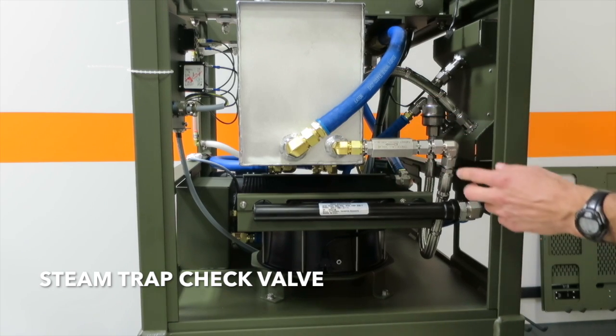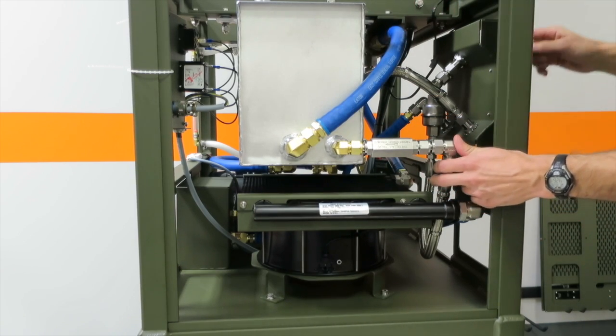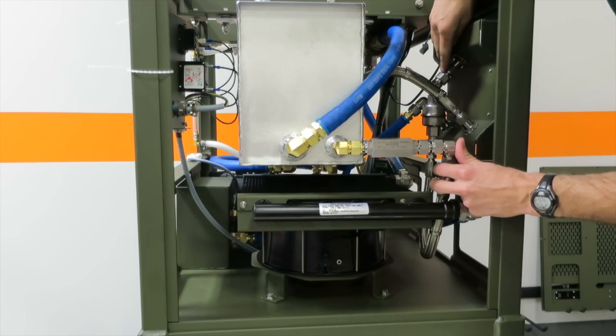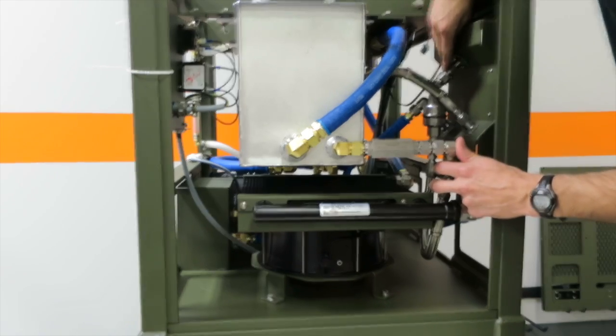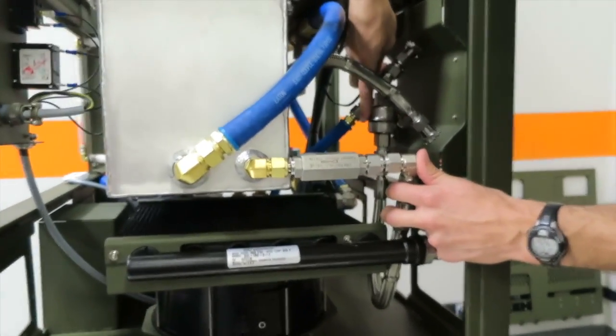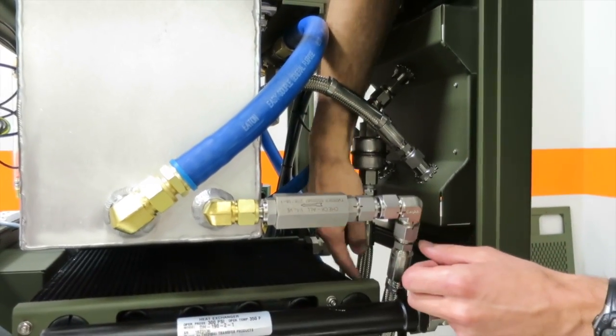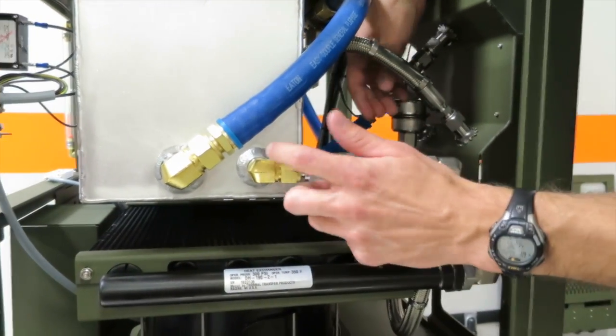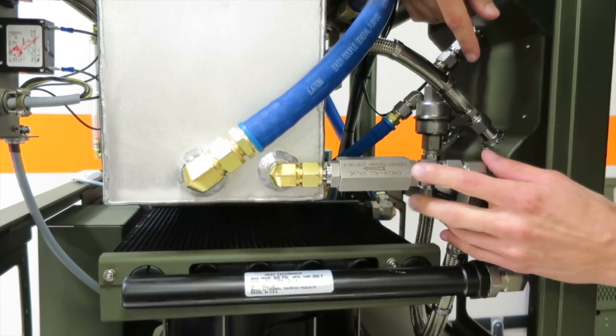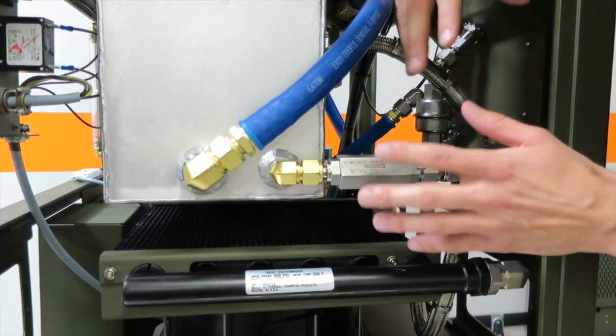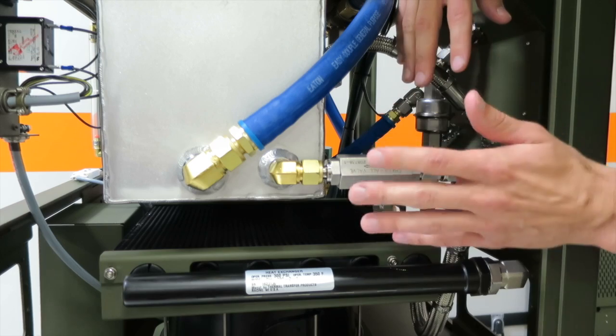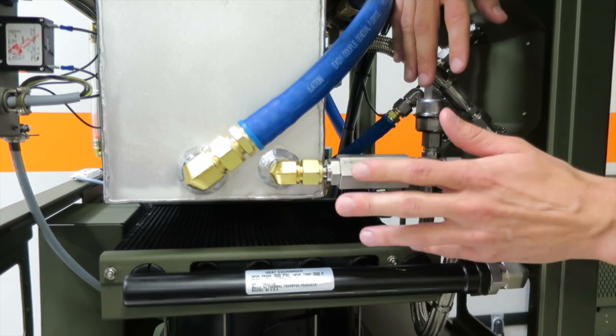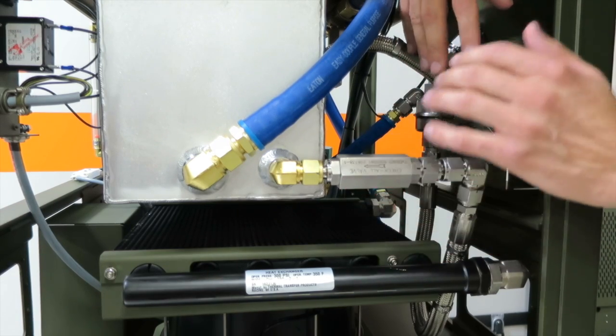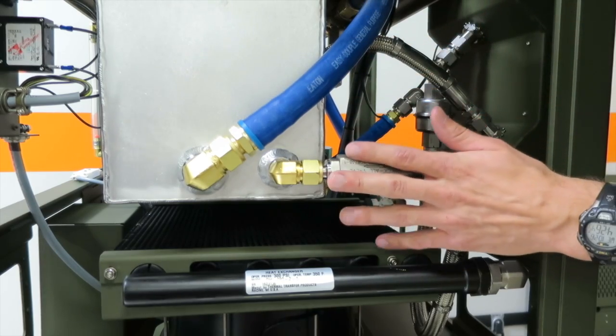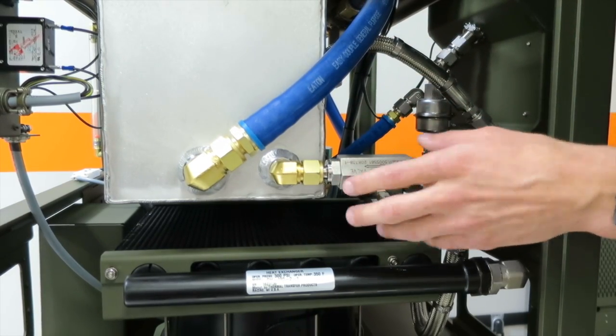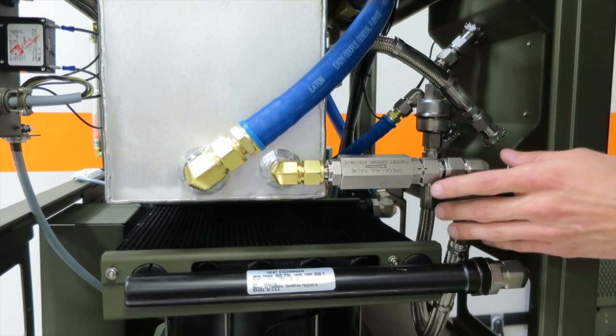So here's the steam trap right here, and whenever condensate is forming in the chamber of the sterilizer main unit, it's going through the steam trap, through this hose, through this check valve, and back into the tank. So this is where we are recovering all the condensate formed during a sterilizer cycle. So this is why this unit is called a water recovery system, because we're recovering the water throughout a cycle.